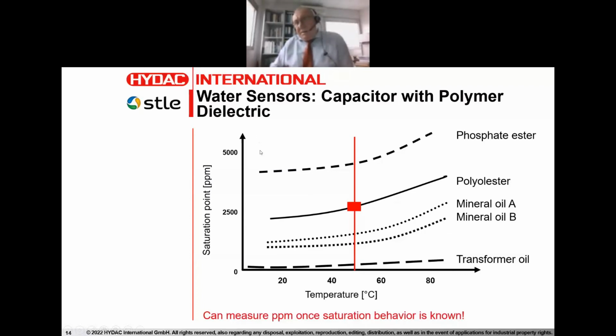And another most interesting example is polyalkylene glycols, which actually exhibit the negative trend. And the reason is that they are prone to hydrogen bonding that occurs at low temperatures. So the water is bound to the backbone of the molecule and does not manifest as free water molecules, or dissociated water molecules, not free as in free water phase, but dissociated water molecules floating around the system. So they don't migrate into the sensor, and the sensor misses them. As the temperature goes up, that hydrogen bond, which is a relatively weak bond, is broken, and this water dissociates, and these dissociated molecules are released. So less additional water is then required to saturate the fluid. So the curve is actually going in a reverse direction.